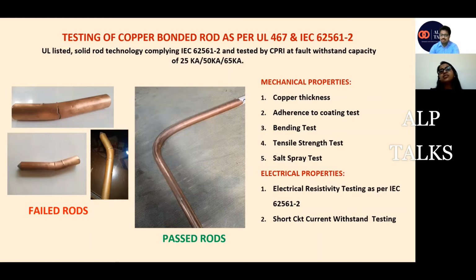Other than this, for the electrical test, there is the fault current carrying capacity. As per the size of the rod and the requirement of fault current, we do the CPRI testing of these rods. So this ensures the quality of the rod and the life of the rod, which we cannot rely on over pipe earthing or plate earthing. With pipe earthing and plate earthing, the only thing we can test is the fault current carrying capacity. For that, I just need to go to CPRI.